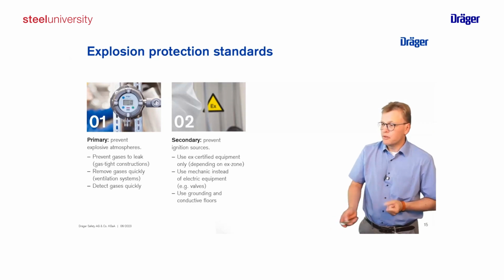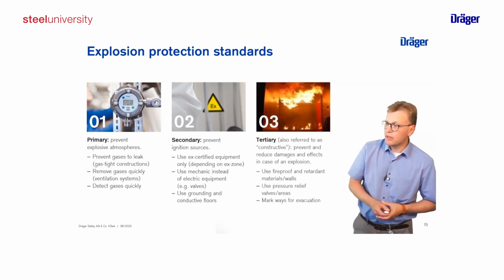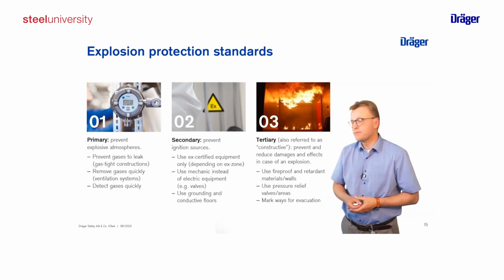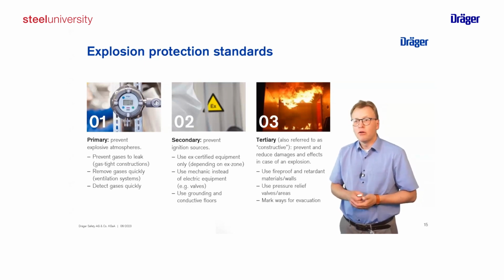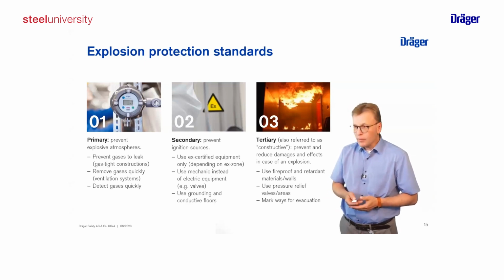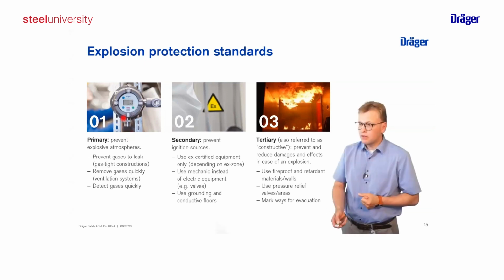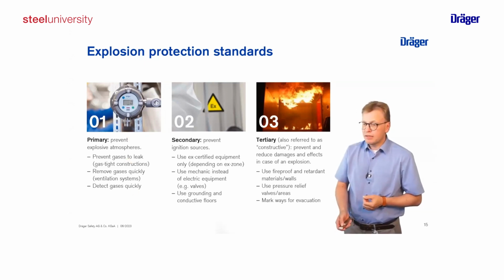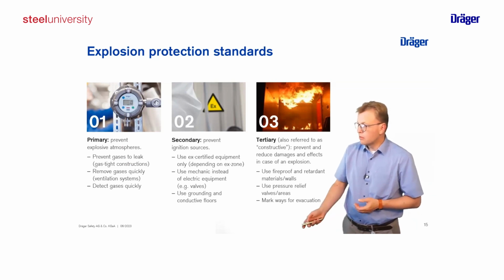If this is all done, nevertheless there could always be the risk that you still have an explosion, then the third level is what we call the constructive measures. So we design our application, our processes, so that the propagation is reduced. So the effect of an explosion is limited. Using materials which are fire retardant or fireproof, you use pressure release valves, or breakthroughs in the walls so that the pressure is released so that we don't have a collapse of the building. For our presentation today, it's important we will concentrate on the primary pillar. So we want to prevent, and as we speak about gas detection, the good message is here.